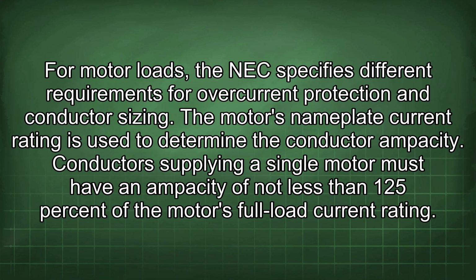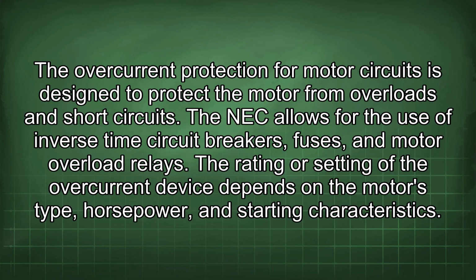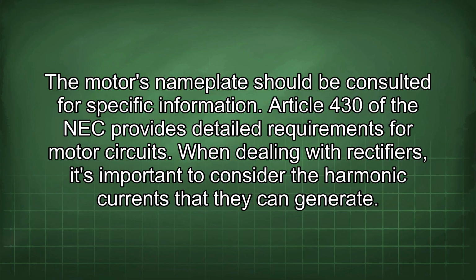For motor loads, the NEC specifies different requirements for overcurrent protection and conductor sizing. The motor's nameplate current rating is used to determine the conductor ampacity. Conductors supplying a single motor must have an ampacity of not less than 125% of the motor's full load current rating. The overcurrent protection for motor circuits is designed to protect the motor from overloads and short circuits. The NEC allows for the use of inverse time circuit breakers, fuses, and motor overload relays. The rating or setting of the overcurrent device depends on the motor's type, horsepower, and starting characteristics. The motor's nameplate should be consulted for specific information.